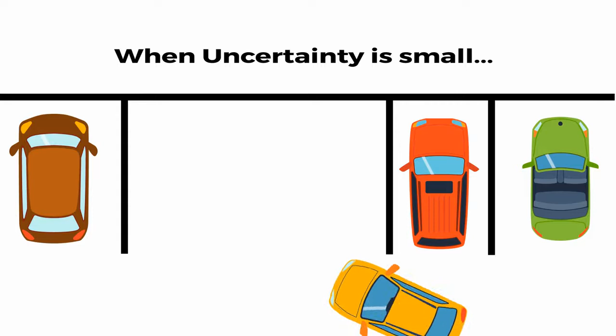Measurement uncertainty also keeps us honest. If we think about making a conformity assessment of pass or fail, the larger your measurement uncertainty, the more likely you are to fail an instrument. Using the analogy of a parking space, when your uncertainty is small, you have a large parking space to easily park your car. This small uncertainty means we have more space or range to pass an instrument. However, when your uncertainty is large, you have the smallest parking space, sometimes with not enough room to park. You have less range and sometimes no range at all to pass an instrument.